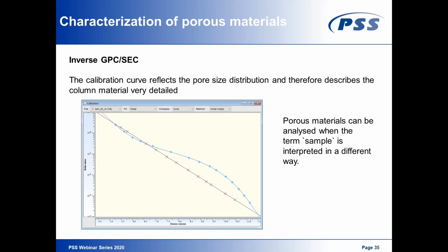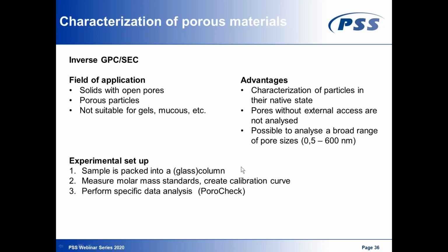Keeping that in mind and going back and defining sample in a different way, you can maybe already guess what inverse GPC SEC means. In inverse GPC SEC, we perform a completely different analysis. We use our sample as column material, which means we pack our sample into a glass column. Fortunately, the packing efficiency is not important here. And then we measure molar mass standards again to create a calibration curve. And then we can transfer this calibration curve using specific data analysis, like for example our PoroCheck, into the pore size and the pore size distribution.